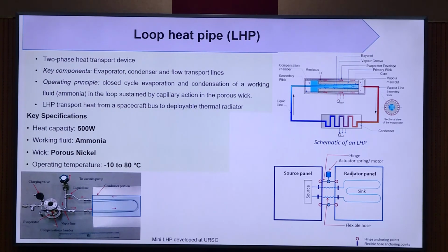Whatever we have developed so far is a 500 watt ammonia loop heat pipe with porous nickel, because of the nickel we have used, and the operating temperature is between -10 and 80. This is the picture of the mini loop heat pipe developed at URSC with a flat plate evaporator. This picture shows how we link the source panel, where all the evaporator components will be, and the radiator will be connected with a condenser zone, and there will be a flexible link between the evaporator and the condenser.